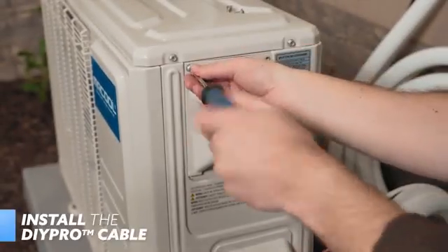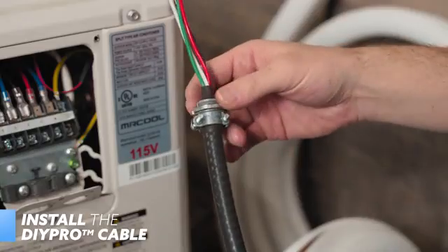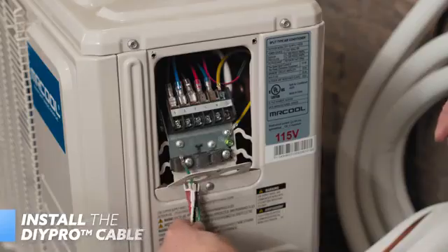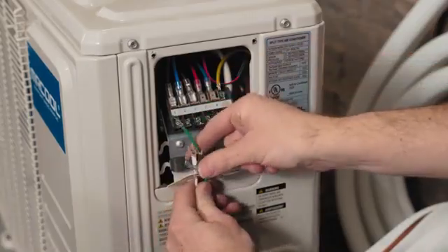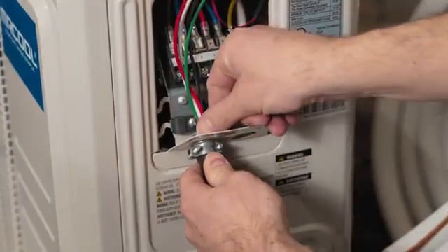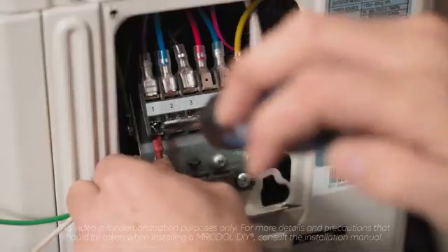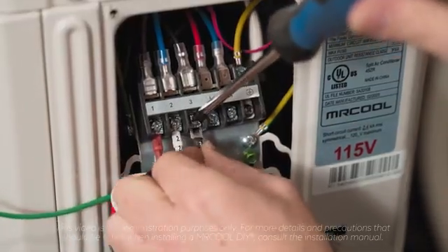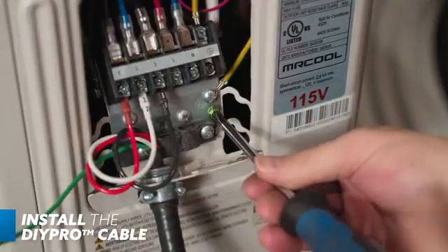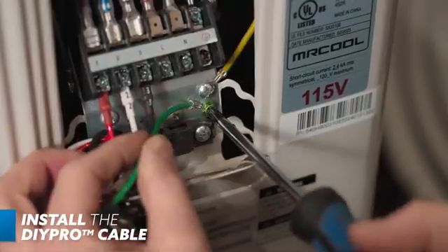Up next, remove the wire cover from the unit by loosening the screws attaching it to the condenser. Then remove the ring from the DIY Pro Cable by turning it counterclockwise. You'll pass the DIY Pro Cable through the hole on the left of the metal panel before re-securing the ring, thereby securing the cable to the panel. Then you'll connect each wire to its component terminal, with one going to one, two to two, and three to three. The green ground wire will be secured by the green screw on the terminal plate — it will be unscrewed, placed inside the green wire's hole, and then re-screwed into the same hole on the terminal plate.